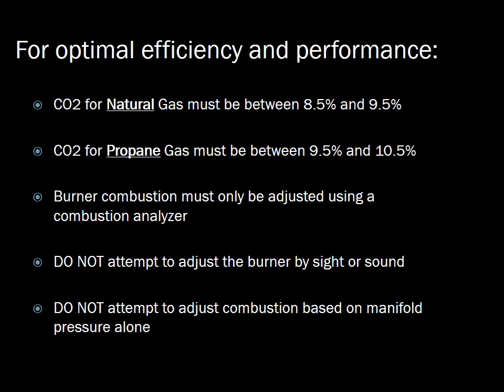For optimal efficiency and performance, the CO2 for natural gas must be between 8.5% and 9.5%. For propane gas, the CO2 must be between 9.5% and 10.5%. Burner combustion must only be adjusted using a combustion analyzer. Do not attempt to adjust the burner by sight or sound. Do not attempt to adjust combustion based on manifold pressure alone. Manifold pressure should only be used as a reference point.